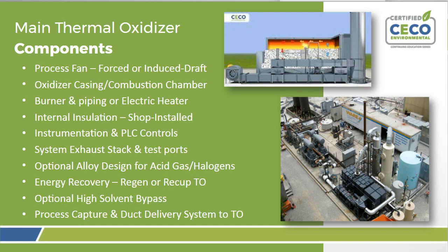Otherwise, you may be feeding into other process equipment like a tower scrubber for post-treatment of acid gases, for example. But anyway, nowadays the RTO, regenerative thermal oxidizer, is probably the most common of all, which also has heat recovery beds to minimize fuel usage. That's a really important part of the way that it operates. That's the most common that you'll see.